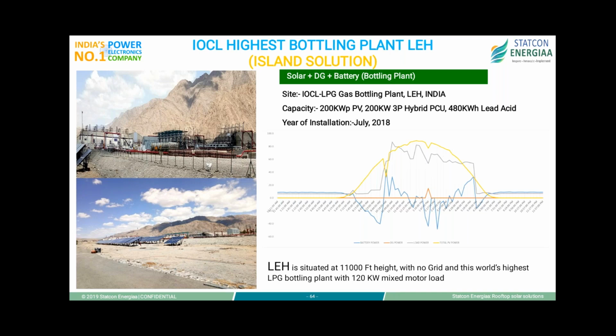They initially installed a 100 kilowatt system and found their DG running reduced by 70%, so only 30% DG running remained. They then increased their PV capacity to 200 kilowatt, and now use the DG set only during storms or when solar generation is not available at all. This is a typical example of how, if well designed, such isolated sites can also work on solar.